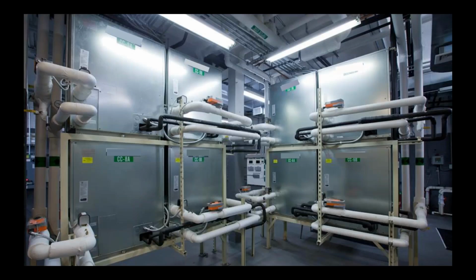Now, the other thing is people worry about heat pump systems being challenging to maintain, right? Normally you think of a heat pump like a VRF system. You think of a bunch of condensing units out on the roof, right? A whole farm of condensing units for a big building. You have to go out on the roof on a snowy day and fix a piece of equipment that's failed to make sure you get some heat. Well, what we're doing here is very different.